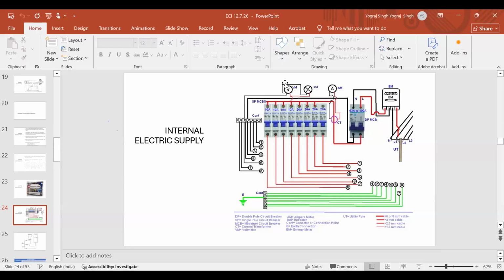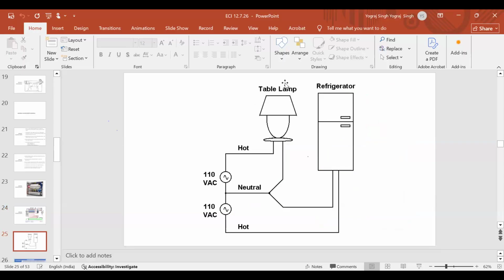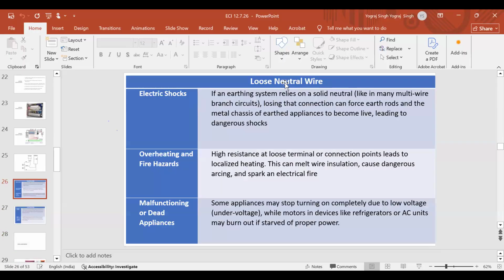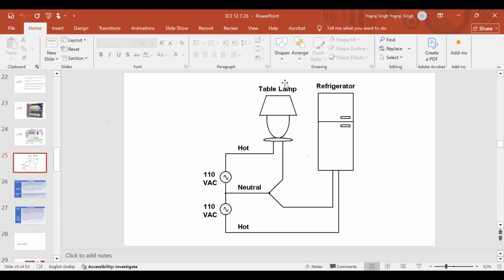RCCB, now when the wiring is done, you check the wire for continuity, insulation test, and polarity test. What is polarity test? Means my switch should be in phase conductor only, not in neutral conductor. Suppose I provide the switch in neutral conductor, so light will still be off, but it is dangerous because phase is directly connected all the time. So polarity is important. That switch has to be only in phase conductor.